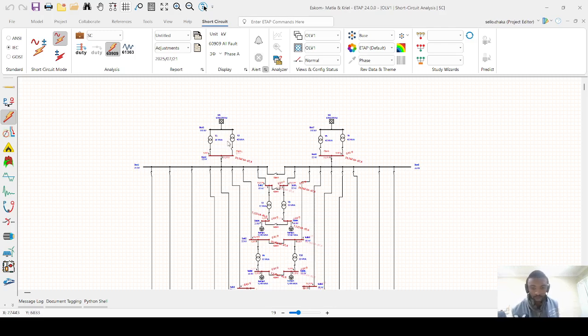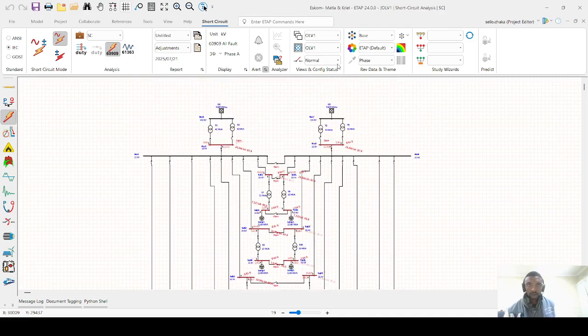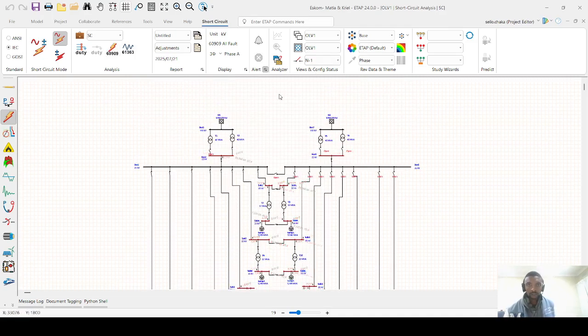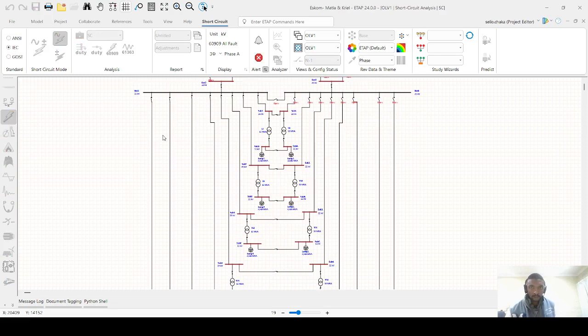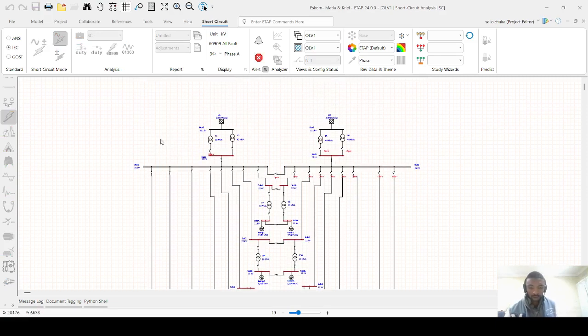According to this, you can see that the fault level closest to the source is the highest at 24 kA, and the secondary low voltage side values align with the main busbar circuit, confirming transformer sizing and protection is adequate. And then this is for N-1. When I run the short circuit, you'll see the results.